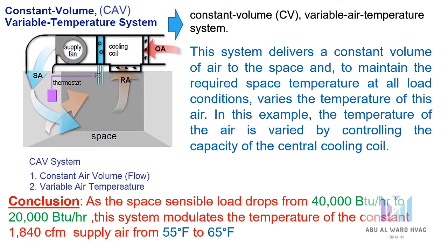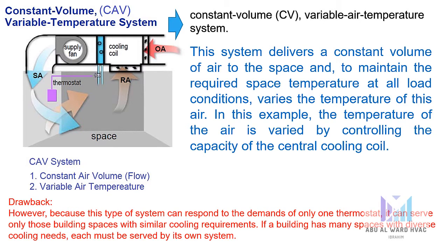As the space sensible load drops from 40,000 BTU to 20,000 BTU, the system modulates the temperature of the constant 1,840 CFM supply air from 55°F to 65°F. The drawback is that this type of system can respond to the demands of only one thermostat, so it can serve only buildings with spaces that have similar cooling requirements. If a building has many spaces with diverse cooling needs, each must be served by its own system.